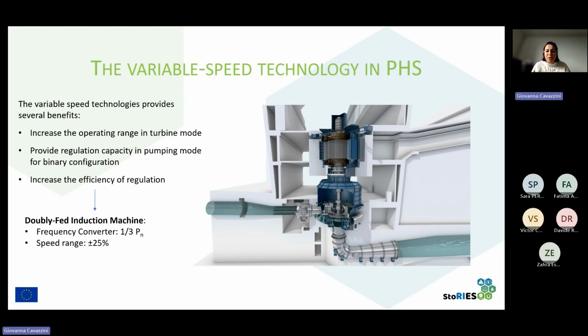This variable speed option has been enabled with significant innovation regarding the electrical machine of the power plants. In particular, the technology of the doubly fed induction machine has been introduced. In this technology, a frequency converter with a power equal to 1/3 of the nominal power of the power plant has been introduced, and this has enabled the possibility of varying the rotation rate of the machine in a speed range of plus or minus 25%.